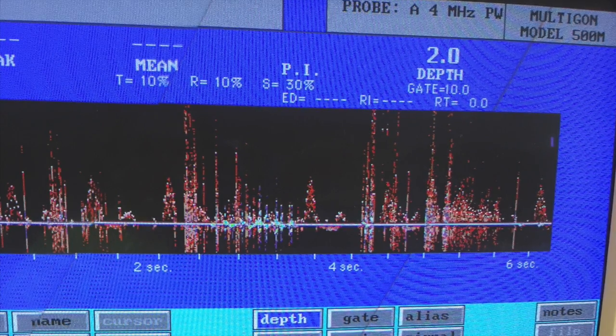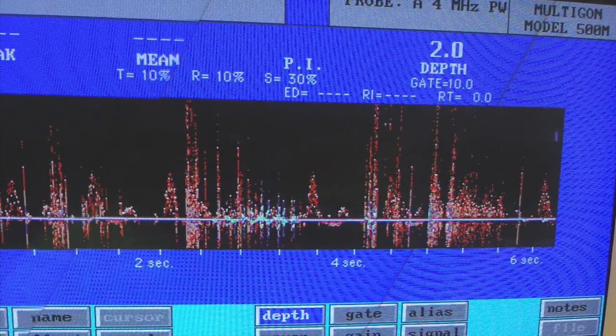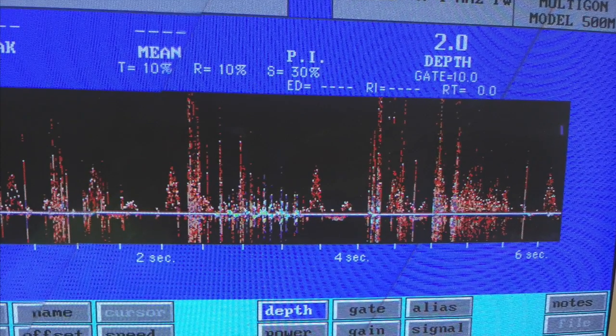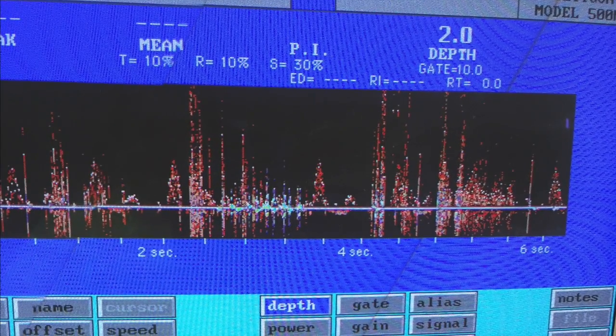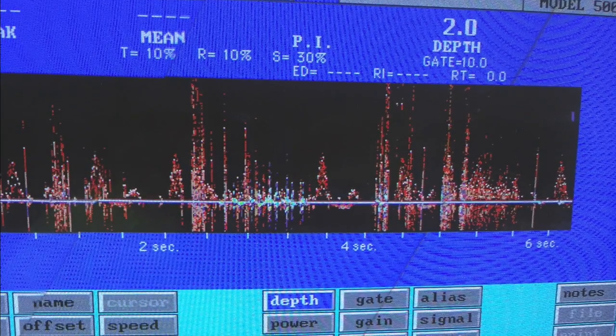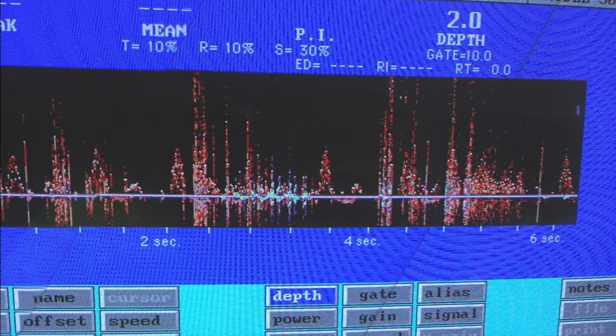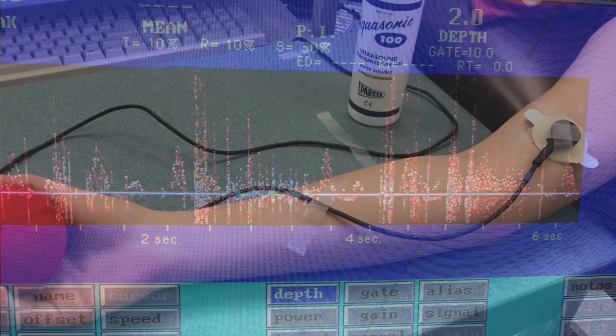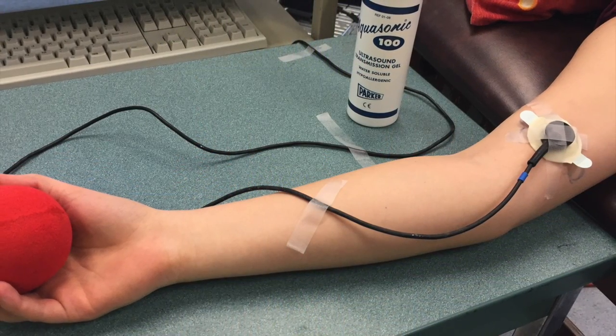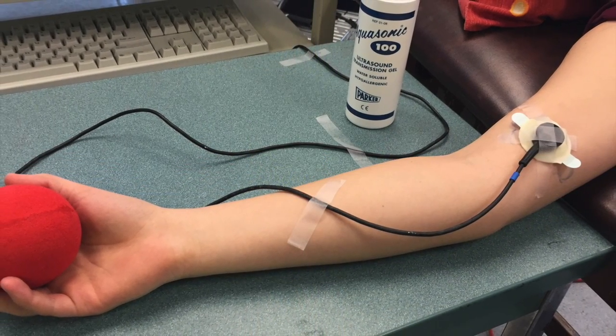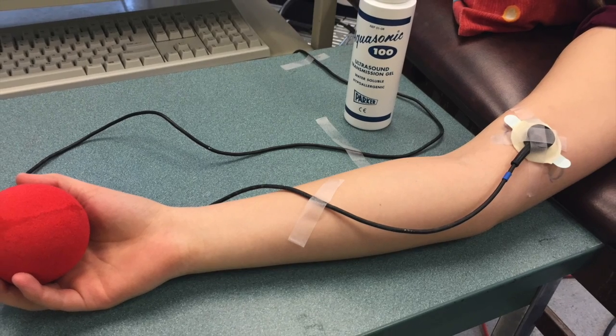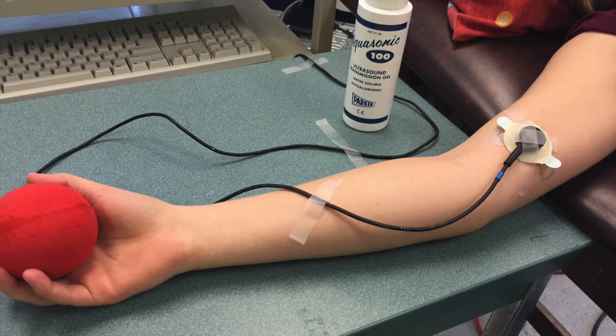One of these factors is noise. This graph shows how noise can interfere with the blood velocity signal. If the wire moves around too much, there can be a lot of noise, causing a weaker and less clear signal to be seen. This can be fixed by taping down the wire to reduce movement, as shown in the picture. This produces a much clearer image, allowing us to have a better reading of blood velocity.